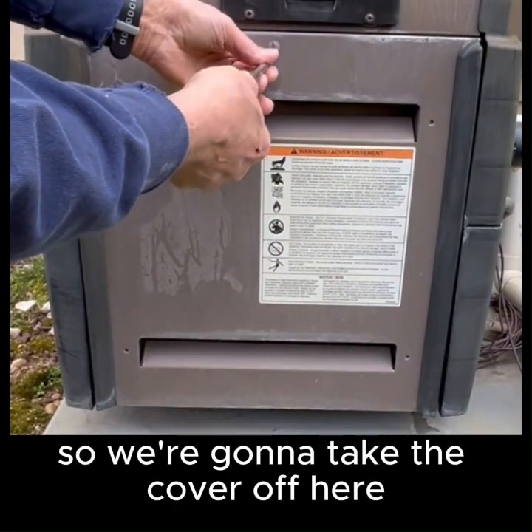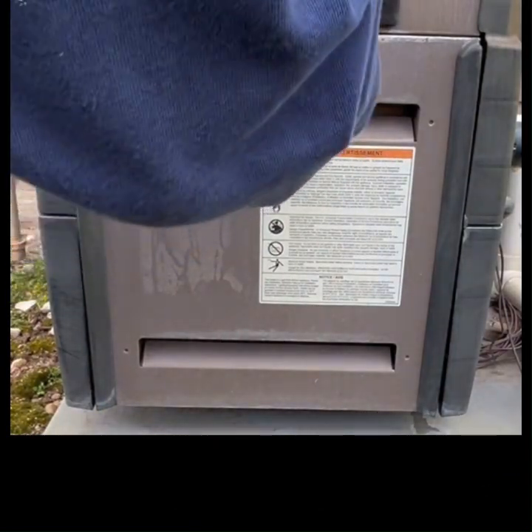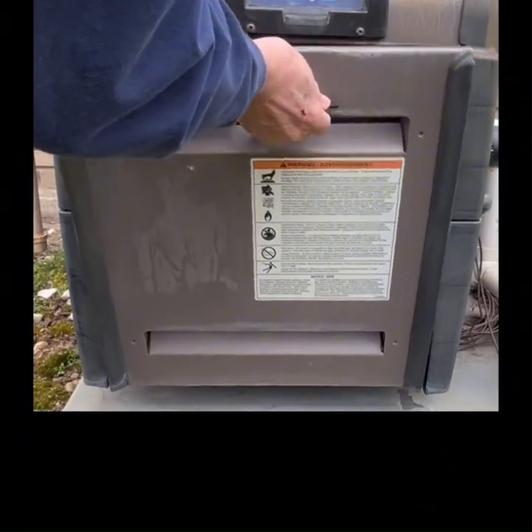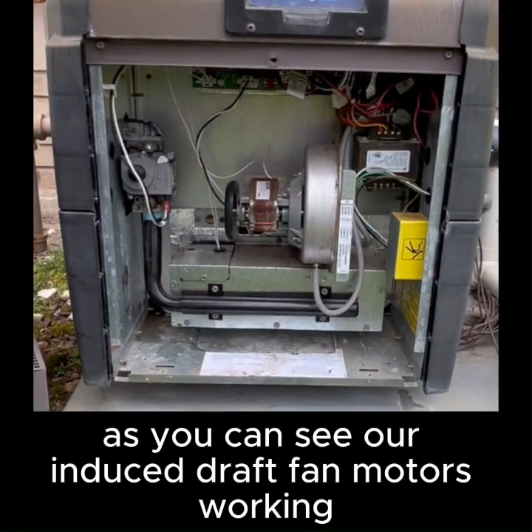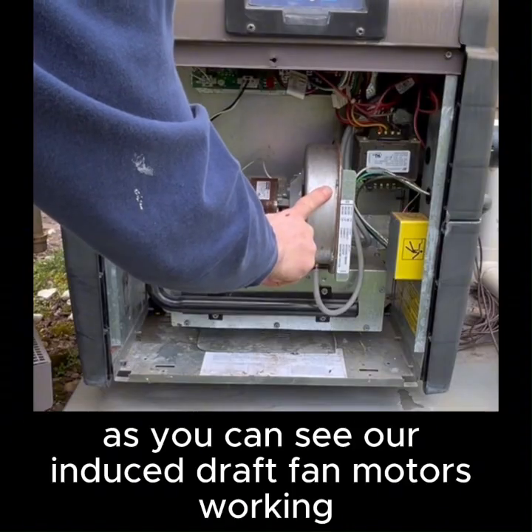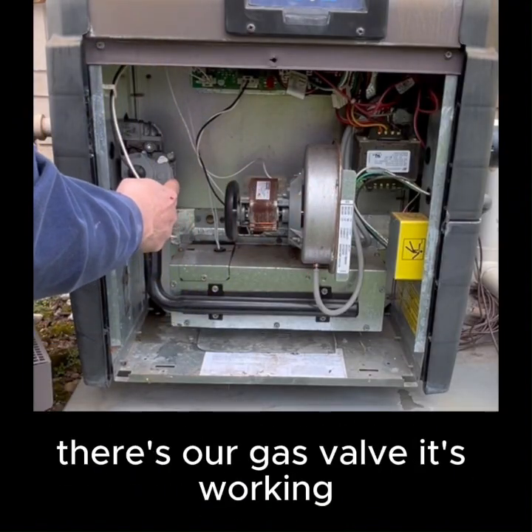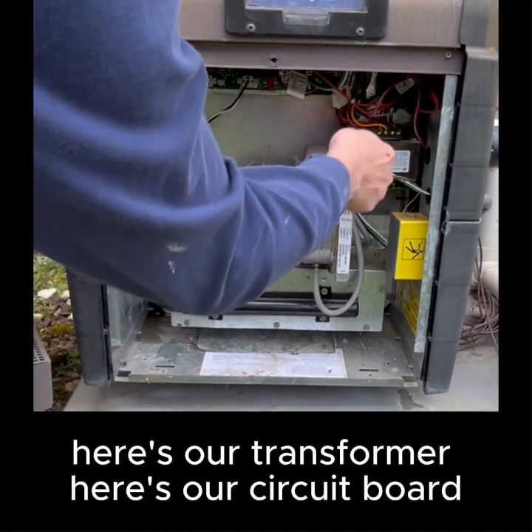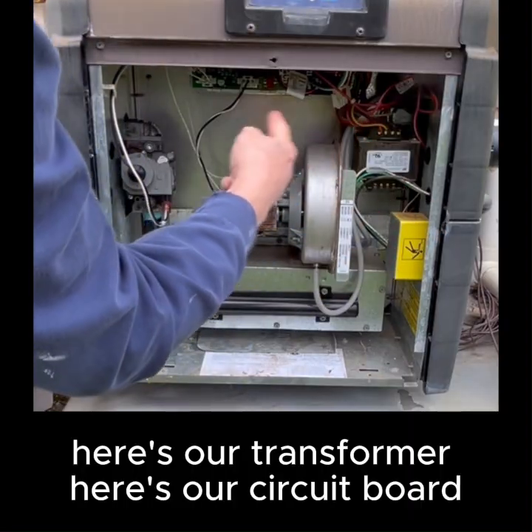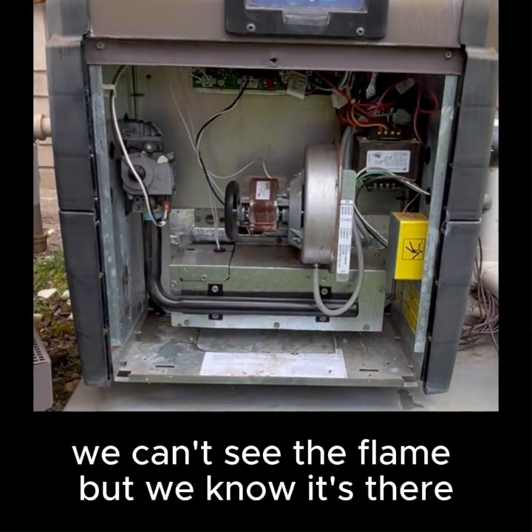So we're going to take the cover off here. As you can see, our induced draft fan motor is working. There's our gas valve, it's working. Here's our transformer. Here's our circuit board. We can't see the flame, but we know it's there, obviously.